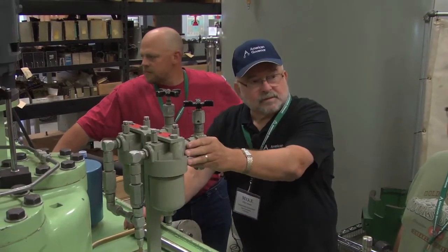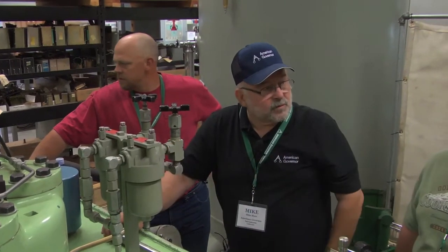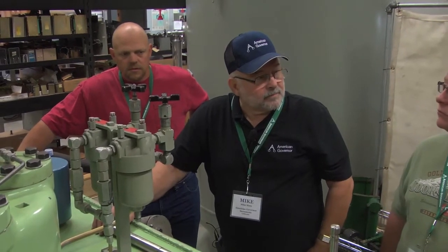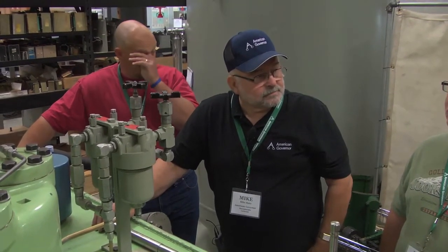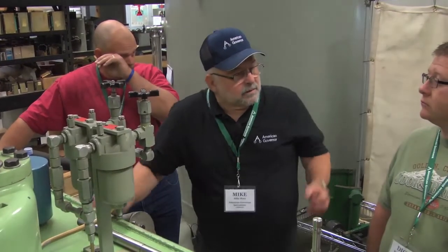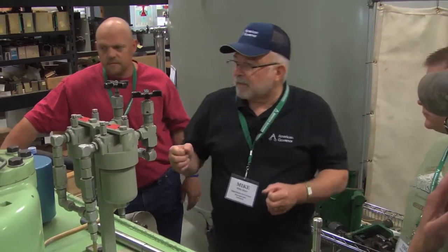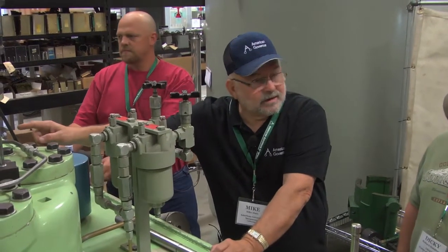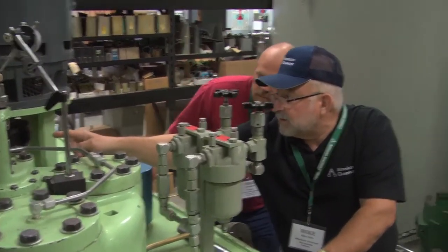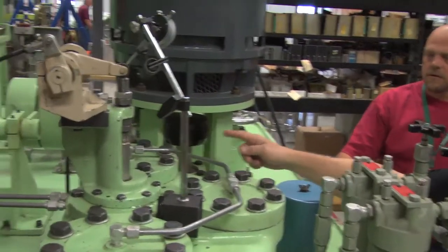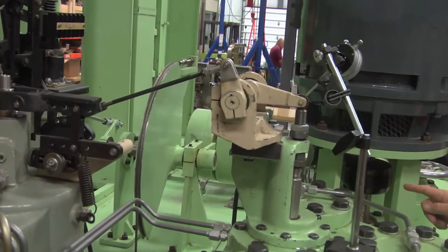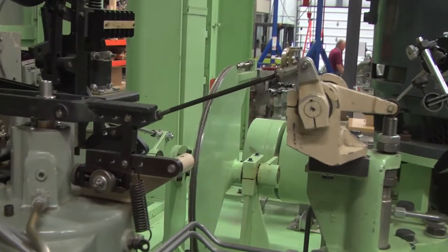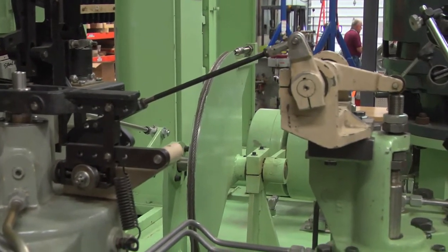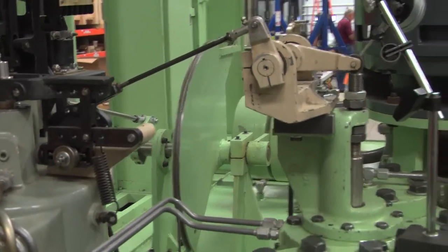3.5 foot stroke. 3.5 foot? Wow. For our wicket gate ring, that's stroking about 3.5 feet. Well, the stroke is always proportional to your sheave. See the center line of that sheave right there, the center of it where it has a key in it? If you go to the center of that rod, out to where the wire lies, that is the stroke of the unit it's on. So that'll tell you where your stroke is. And it's got a little bit of play either way that you take out with eccentrics when you calibrate it.